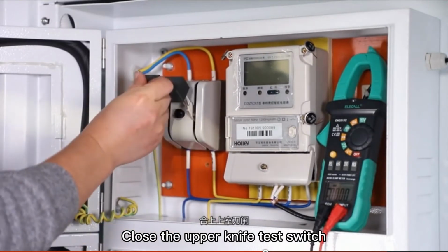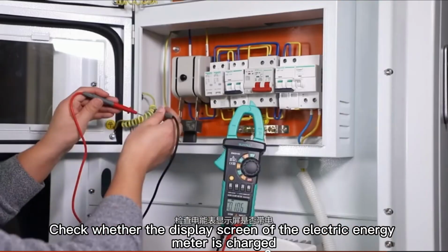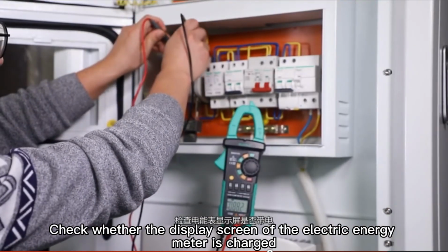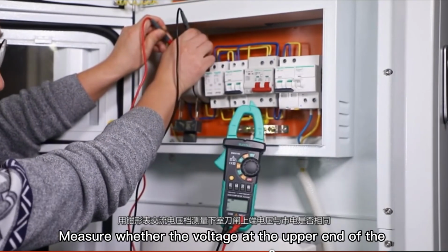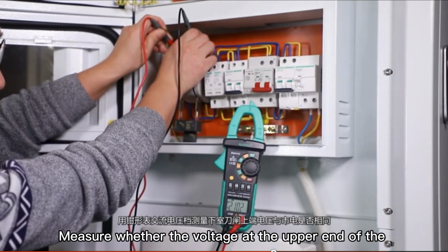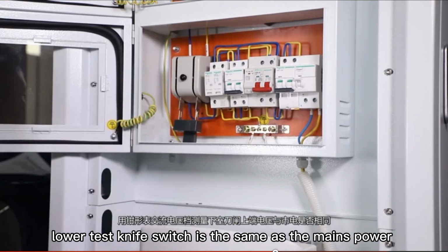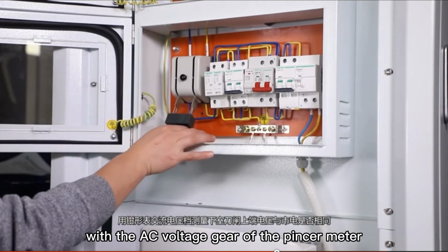Close the upper knife switch. Check whether the display screen of the electric energy meter is charged. Measure whether the voltage at the upper end of the lower knife switch is the same as the mains power with the AC voltage gear of the clamp meter.